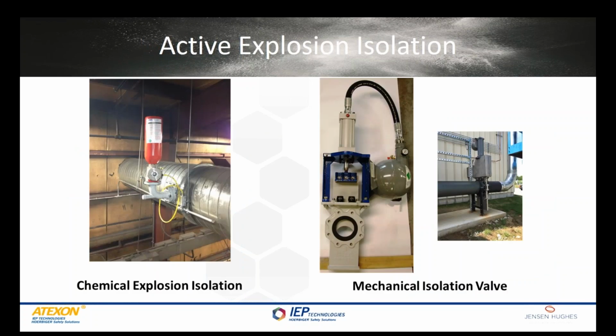The active type systems would typically consist of a detection method, a control panel, and either a chemical or a mechanical isolation barrier that's triggered by that control panel. The detection method can be either the pressure detectors that were shown during the explosion suppression slide, whether it be a static detector or a dynamic type detector, or that detection method could be an IR detector on the duct, detecting flame as it's traveling through, and then very, very quickly discharging extinguishers to create a chemical barrier to arrest that flame as it's traveling through the duct.